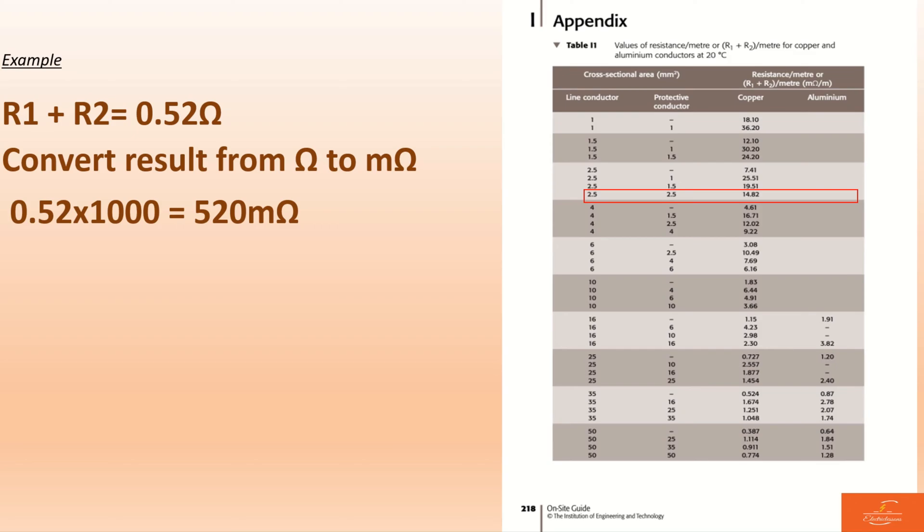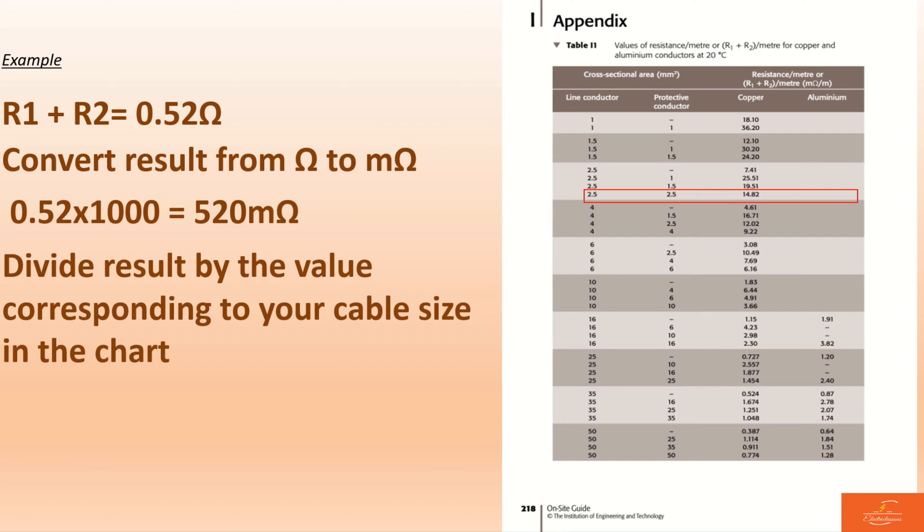Now what we need to do is divide the result by the value corresponding to your cable size in the chart. In our example, what is the value corresponding to a 2.5 cable line conductor and 2.5 protective conductor? We have 14.82. Now what you do is literally 520 divided by 14.82. You'll have 35 and some other values. We just need to approximate.